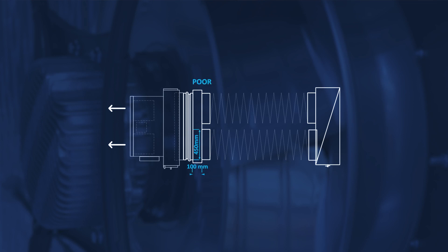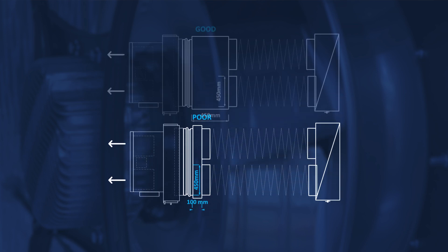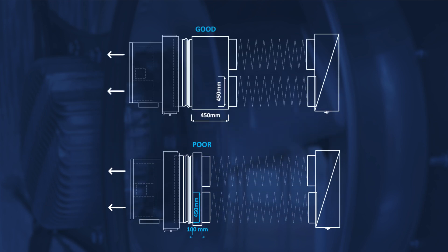Avoid short return air plenums with inlets close to the unit. Unequal static pressure due to turbulence in short return air plenums encourages uneven airflow and high air speed across the indoor coil, resulting in poor performance and water carryover.